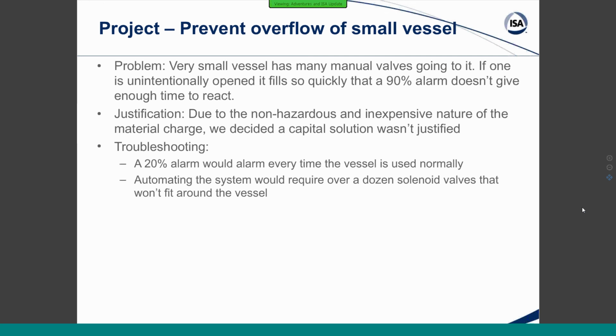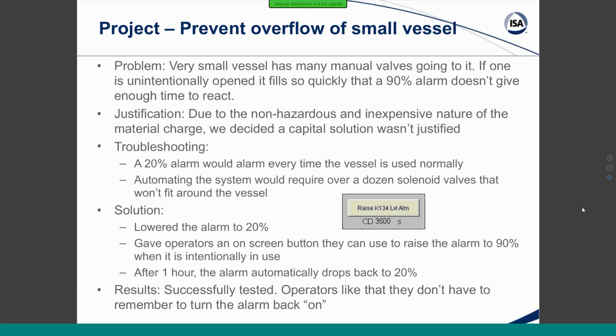Other things that we considered during our troubleshooting: we actually looked at putting the level alarm down to 20%, which works great until you actually try to use the vessel normally. So our solution was to put a snooze button on this alarm. That's what, at least, we're calling it at this point.